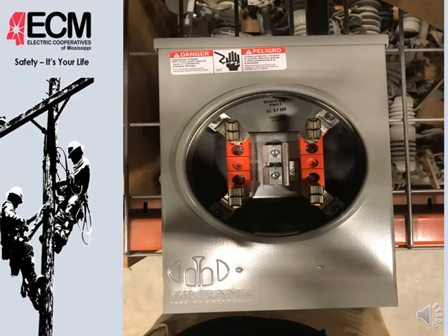I found a brand new meter base in a warehouse. I pulled it out of a box just looking at it. This one here is actually a Milbank meter base, brand new, out of a box, never been used. This is the way this meter base was shipped. What do you notice? If you'll notice, behind the cover of this meter base, the ring that holds the meter in is actually sitting behind the cover. It's sitting on top of the lugs, all four lugs, and in contact with the back of the cover of the meter base.